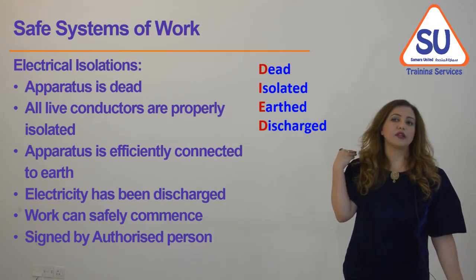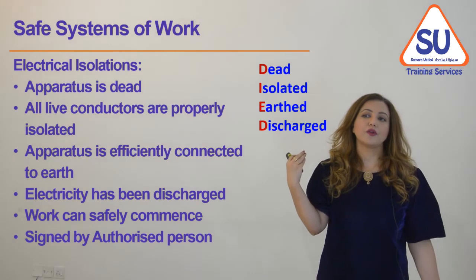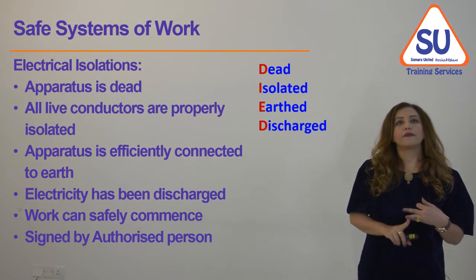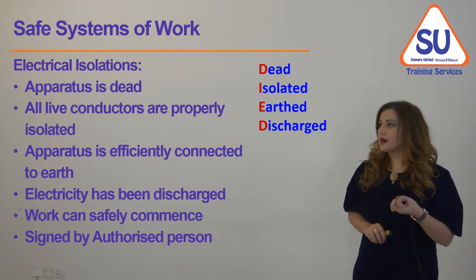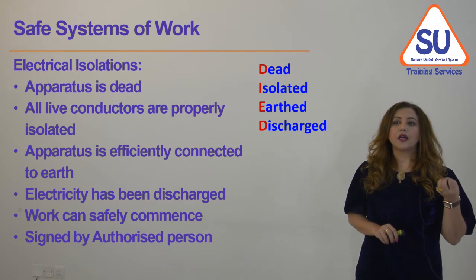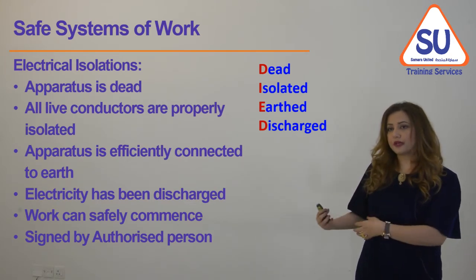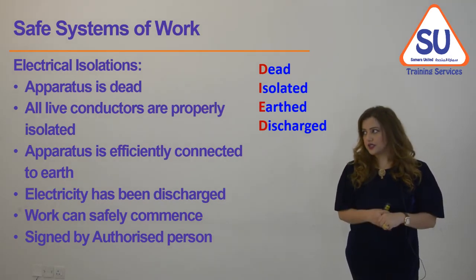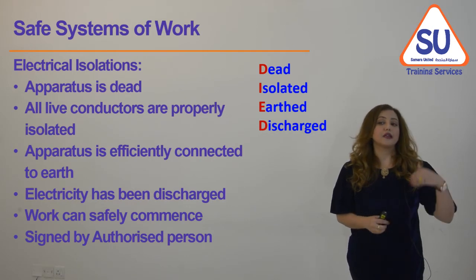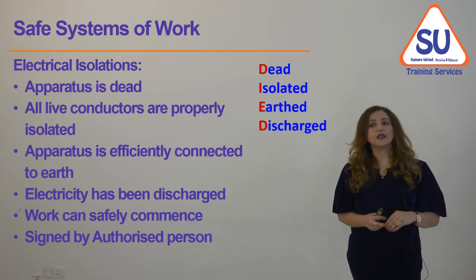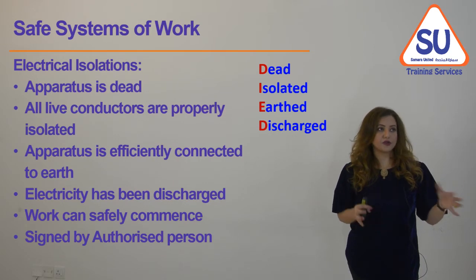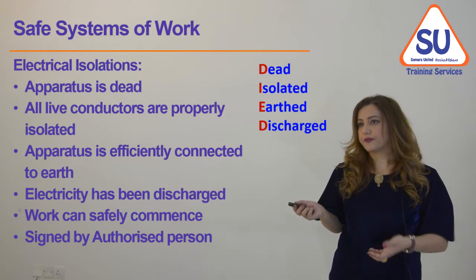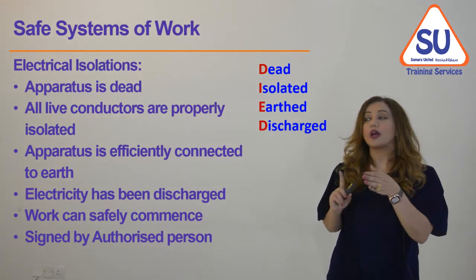What is the safe system of work for electrical safety? It involves electrical isolation — making sure the equipment is dead. All live conductors must be properly isolated and properly earthed, all electricity has been discharged so there is no residual electricity in the equipment, and then a decision can be made that work can safely commence. This must be signed off by an authorized person — a permit-to-work system should be applied. In summary: dead, isolated, earthed, and discharged.